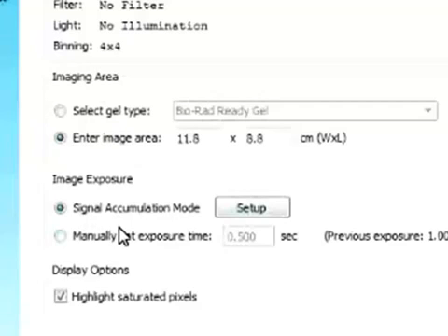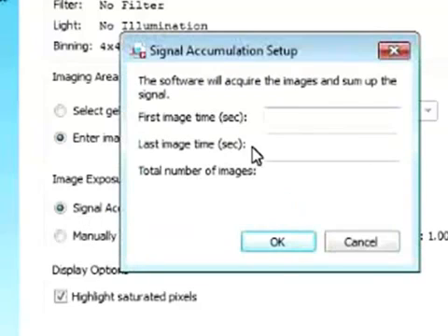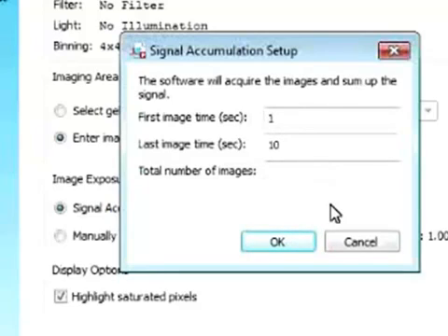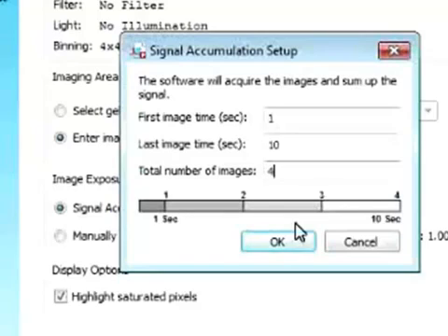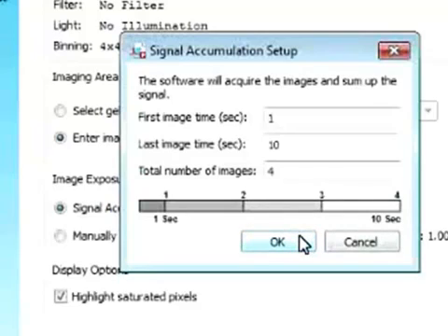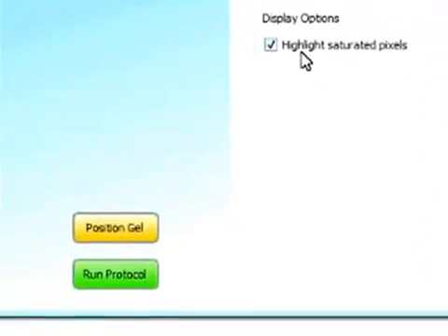We can enter the imaging area. And the nice feature that we have for our chemiluminescent blot is we can set up signal accumulation mode. So if you click on setup, now the software will ask us what is the first imaging time that you want. So we can set to say 1 second. And the last imaging time we can set to 10 seconds. And the total number of images to take, I can select 4. So now the first image will be taken at 1 second exposure. The second image will be taken at 4 second exposure. Third image at 7 seconds. Fourth image at 10 second exposure. So this is a really nice tool that can be used. And you can also select to highlight saturated pixels.